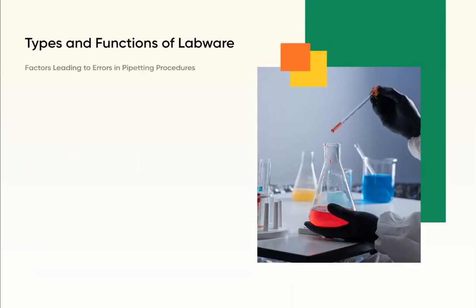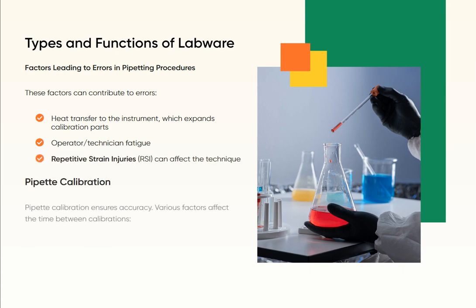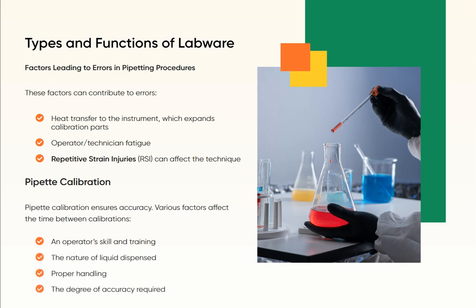Several factors can contribute to errors in pipetting procedures, including heat transfer to the instrument which expands calibration parts, and operator or technician fatigue. Repetitive strain injuries can also affect pipetting technique.